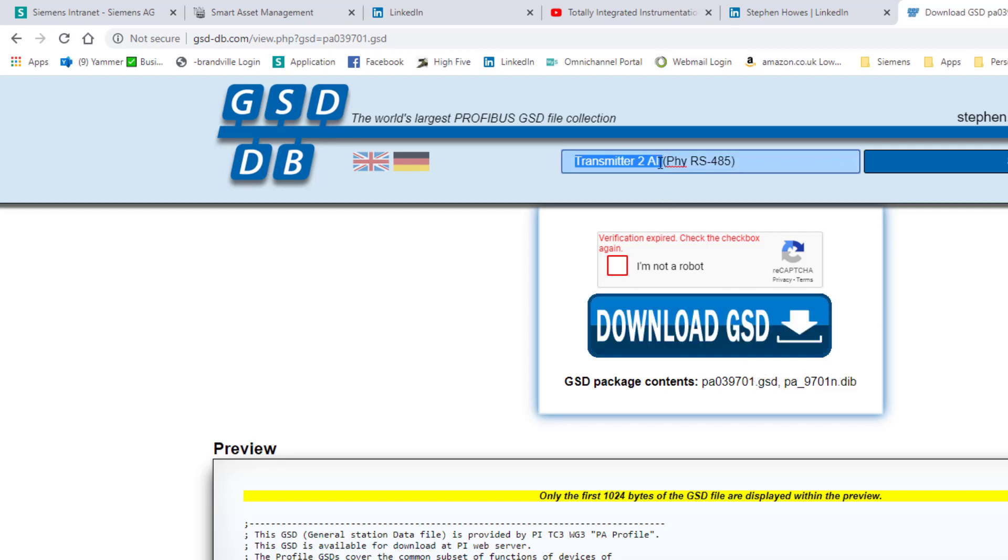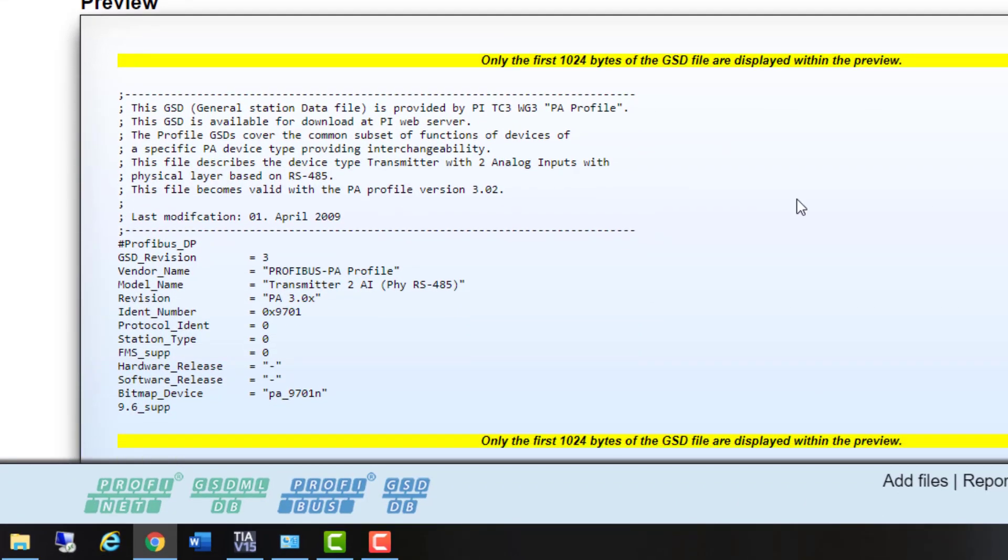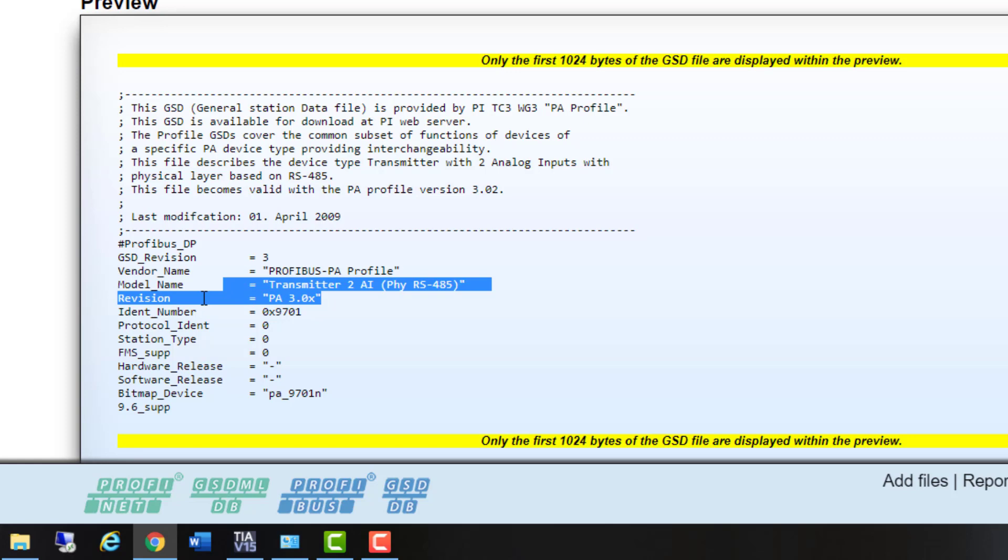This is a transmitter with two analog inputs. The analog input is referring to the PLC, so if you're an instrumentation engineer, we would class that as an analog output, so it's very confusing. But you're always working from the perspective of the PLC. If you look down here, this is just showing you the first bit of the GSD, and you can see it's compatible with any profile three or above instruments that has two analog inputs.